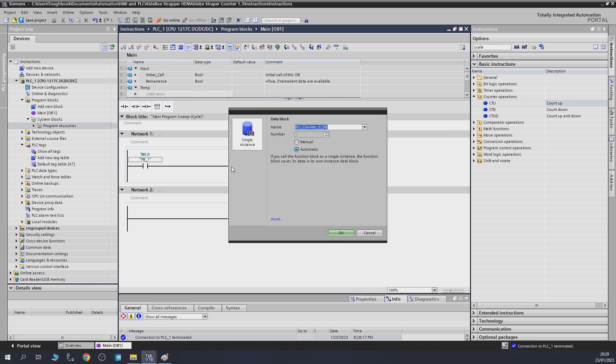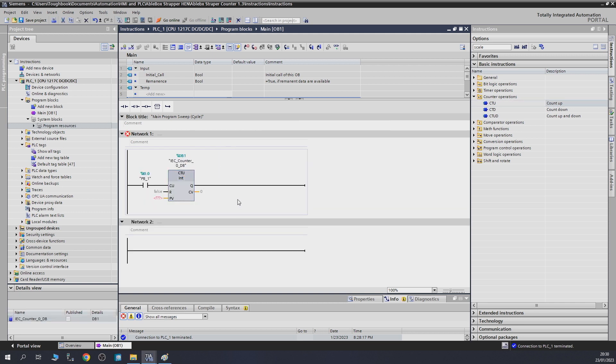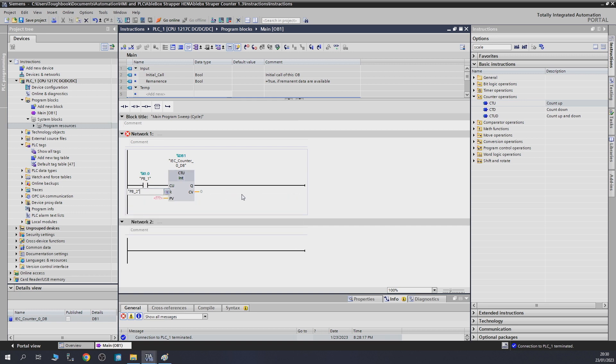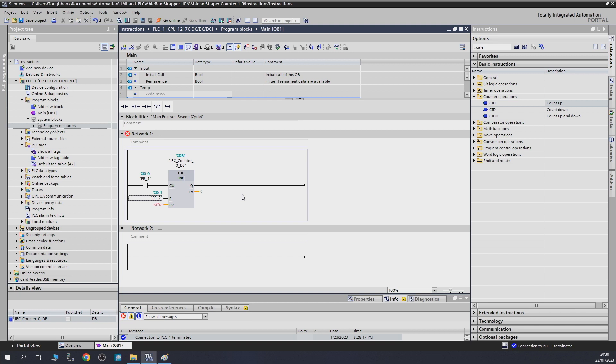Because it requires a data block because it's got values to store, it will pop that up as well. First things first, we've got a reset in here, let's give it a reset as push button two. Once the counter has reached the counted value, it will turn itself on. In the PV we need to tell it how many counts, so it's going to be five.